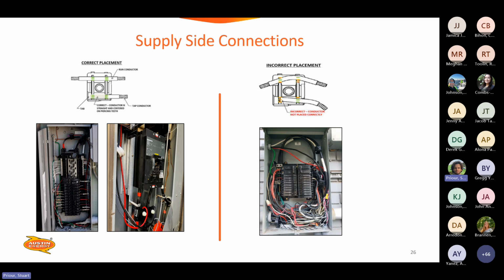And then it spells it out on the left there. That's an incorrect placement. One of those conductors is bent and one is not fully seated into the tapping device. So it's unlikely that you'll find a panel with a side mounted main breaker like that that allows enough space for those extra devices in there. So yeah, not every tap is created the same. I guess think deeply about it before you do a supply side tap. So sometimes it's allowed, sometimes you might need to upgrade that service.